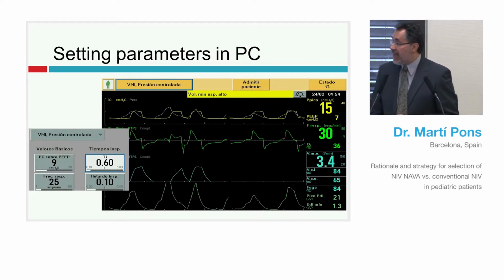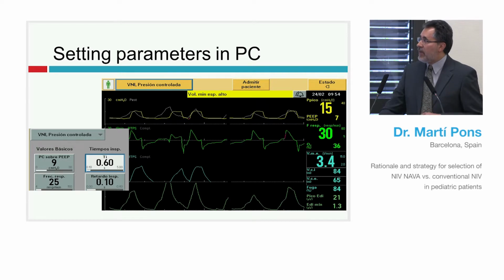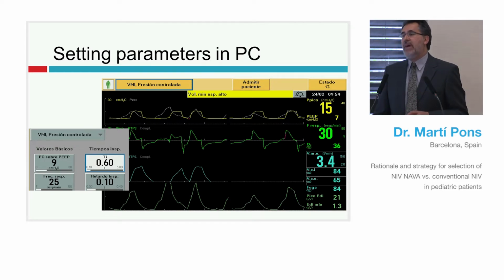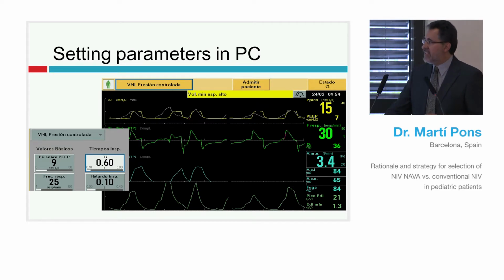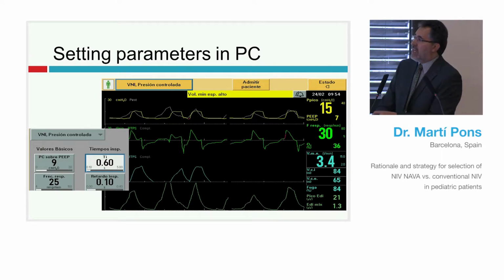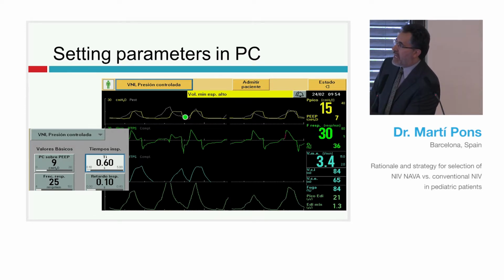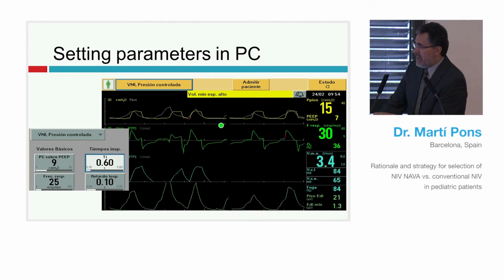We can see also, I think it will be very difficult to see, that in pressure control we have to set the parameters very well. If we do not set the settings properly, we'll have asynchrony. If we set a very long inspiratory time and a low respiratory rate, we can see here with the white line the superimposed NAVA curve, the pressure level that NAVA should deliver. We can see that there is inspiratory asynchrony, expiratory asynchrony, and another wasted effort. So really, if our settings are not good, we are going to fail.